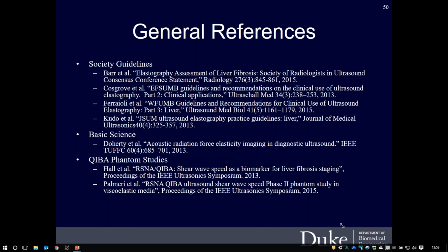So there was a question here about the choice of reporting shear wave speed in meters per second versus what is also a very common metric in the literature, which is kilopascals. As I've alluded to, and as the person asking the question has, Echosens had a lead in the literature on this and has established some of the protocols that have been adopted. Meters per second was chosen I think by the QIBA group because that is what a lot of the underlying radiation force systems were actually directly reconstructing, and then Young's modulus was typically being reconstructed from that speed.